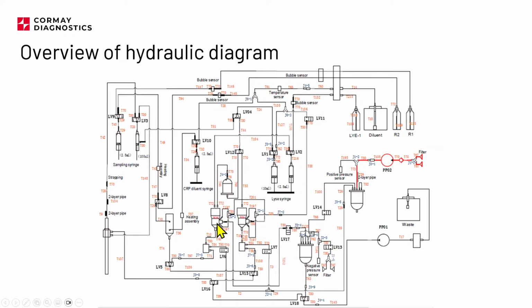So in order to mix everything, the device will push some air bubbles through this port, through the bottom of the chamber, and everything will be mixed inside, because there is no other way: no mechanical mixer, nothing in the analyzer which can mix blood in the chamber. So we rely on the air bubbles. And actually air bubbles are a well-established way to mix the whole volume. Basically all manufacturers of hematology analyzers use air bubbles to mix the blood. This is quite a common way.